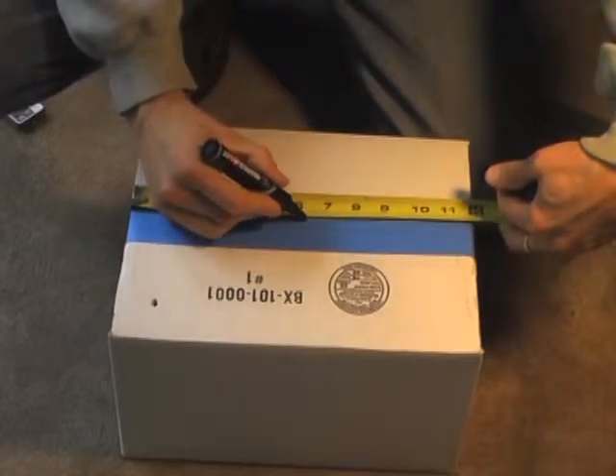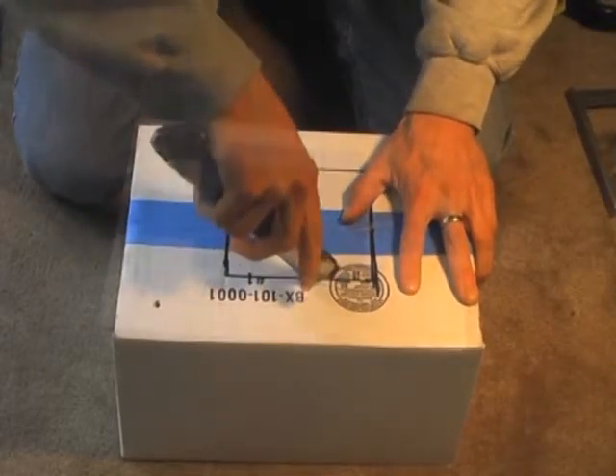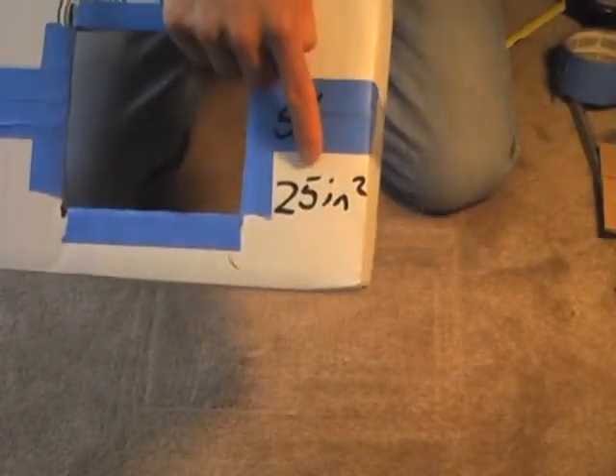Let's go ahead and make our exhaust fan flow box. We're going to select a cardboard box that is big enough to fit over the exhaust fan diffuser — this box should be sufficient. We just need to cut a hole in the bottom of the box. Because we're measuring a bathroom fan, we're going to put a 25 square inch hole in here — 5 inches by 5 inches. We have our box with the hole cut, 5 inches on each side for a total of 25 square inches.